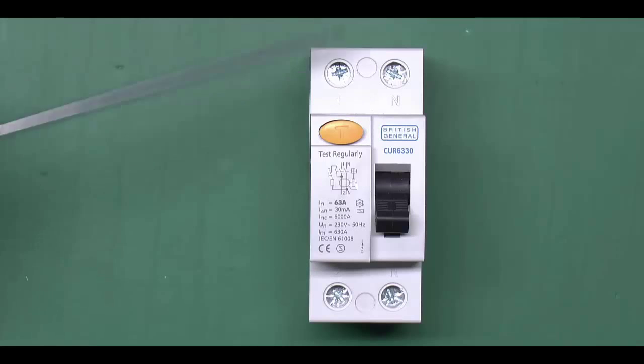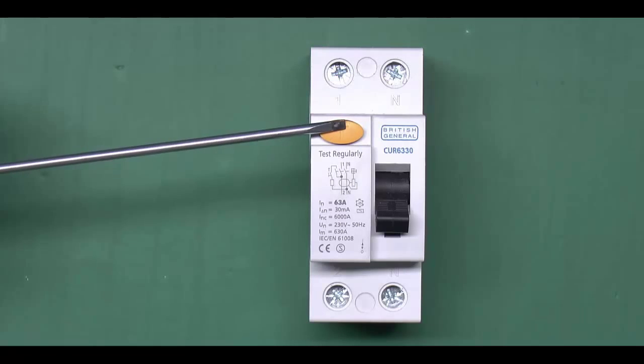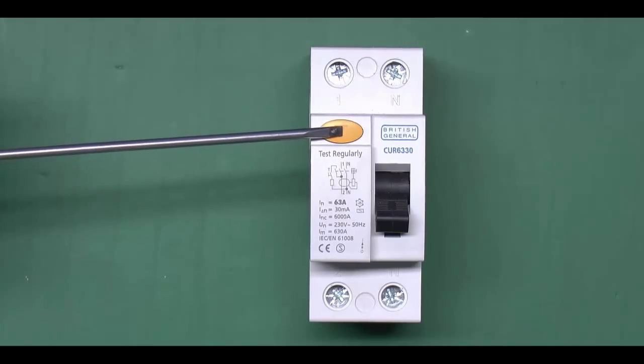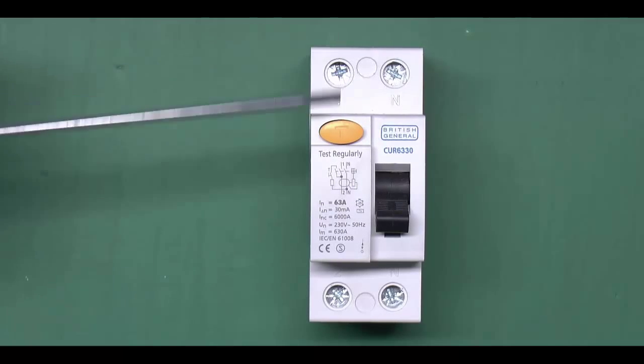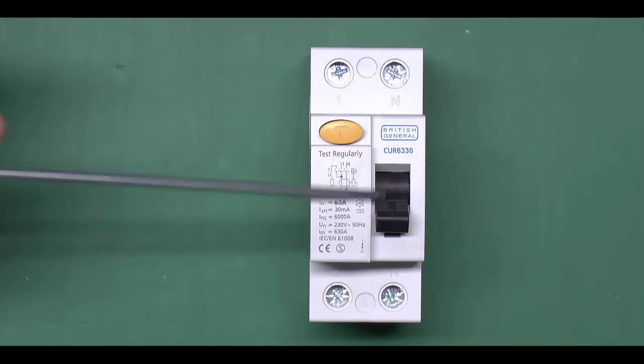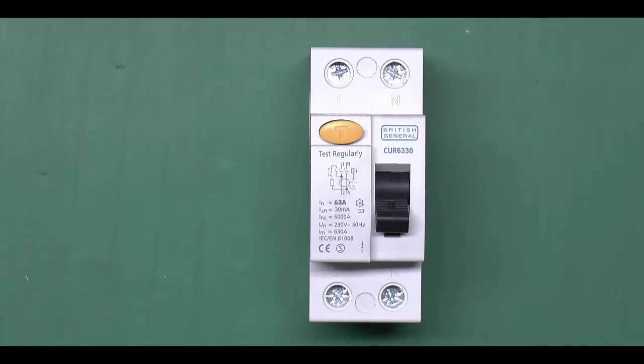And in normal circumstances, of course, those two currents should be exactly the same. If a fault occurs on the load side of the device and the current can then flow to earth via some other path, the current flowing through here is not going to equal the current coming back, and in those circumstances the device will trip and disconnect the supply. Now all of these have a test button on which basically simulates an imbalance in the current. That's just to make sure that the thing will trip, and if you press the button and it doesn't trip, then of course that would indicate a fault with the device and it would need to be replaced.